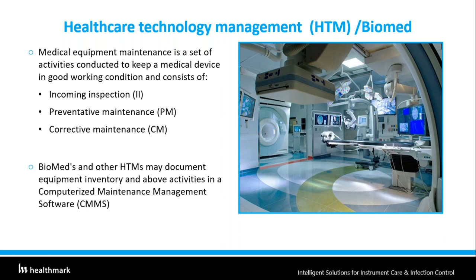So we are going to talk about the role of the healthcare technology manager, HTM, or biomed in the system. As you know, medical technology maintenance is a set of activities performed by biomed or HTM to make sure that the devices are in good working condition. Of course, you need to have a pre-purchase evaluation to make sure that the technology is appropriate for your need. But once it comes to the hospital, biomed will do an incoming inspection to make sure that devices meet manufacturer specifications and check for any damage during manufacturing or shipment. They place them on preventive maintenance based on manufacturer recommendation or the risk level that the hospital comes up with. And when they break, they fix them. And you need to document these either on paper 3x5 cards or, nowadays, in a computerized maintenance management system, or CMMS. Next slide, please.